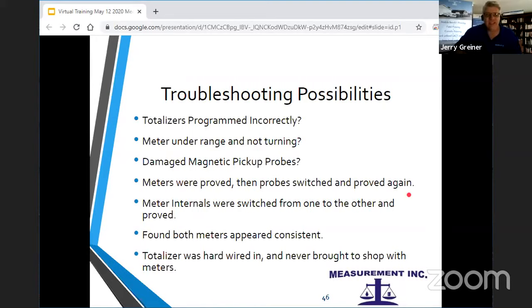And so we asked ourselves, are they programmed correctly? And there's a totalizer on each end, the identical totalizers, both programmed, correct K factor, everything looked good. We couldn't see anything in the totalizers that would be incorrect. Were the meters actually going under range and not turning? Well, it didn't seem like it.